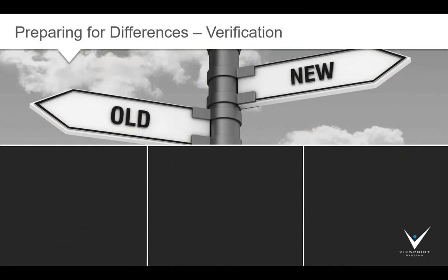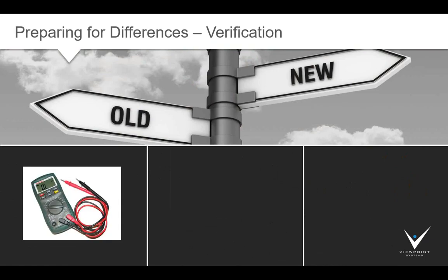How do you know whether the old and new testers are actually the same? There are three methods that you can do to do this. Before you do any of this, make sure that the old and new systems are calibrated. So in this first method, verify that the old and new systems obtain the same readings within some acceptable tolerance. This method neglects any data analysis algorithms that might be embedded in each test step, but for simple test steps which use raw measurement limit checks, this method is good enough, and it doesn't require any UUTs.